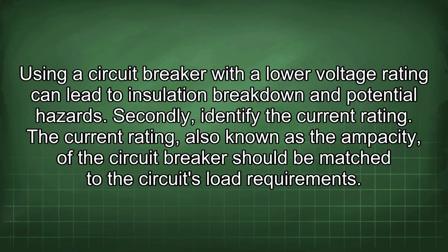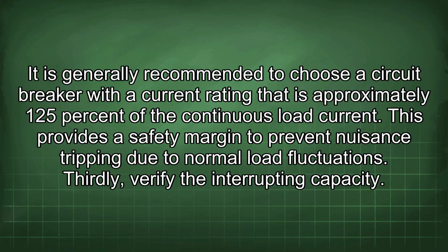The current rating, also known as the ampacity of the circuit breaker, should be matched to the circuit's load requirements. It is generally recommended to choose a circuit breaker with a current rating that is approximately 125% of the continuous load current. This provides a safety margin to prevent nuisance tripping due to normal load fluctuations.